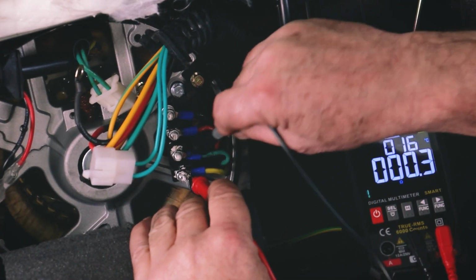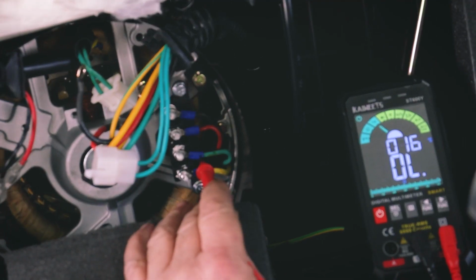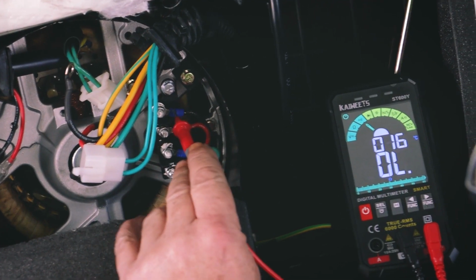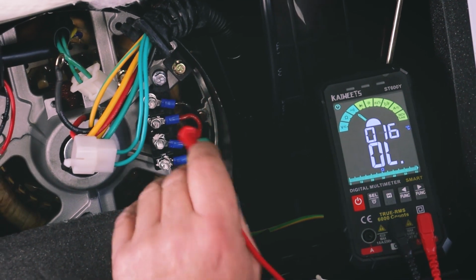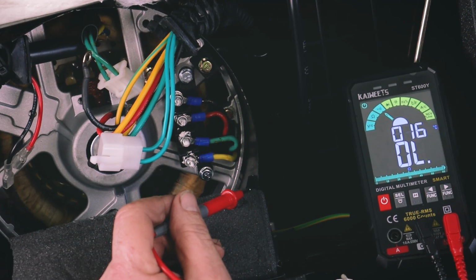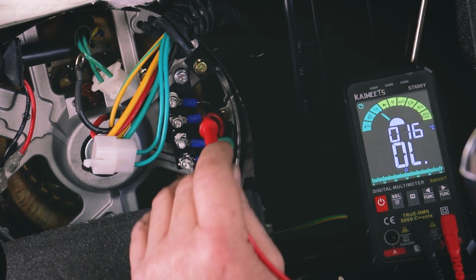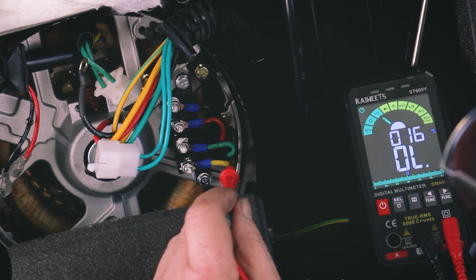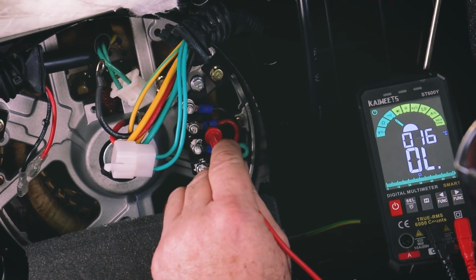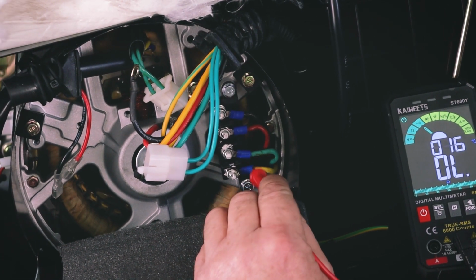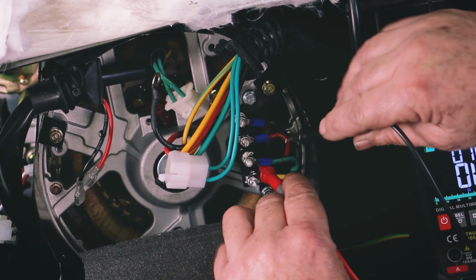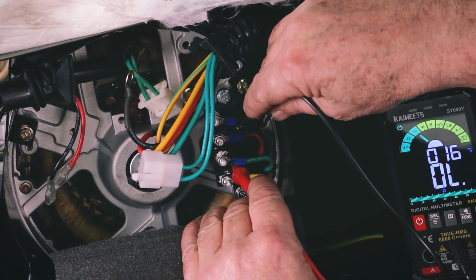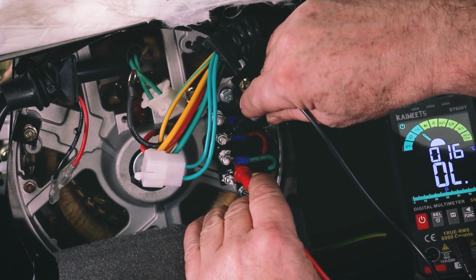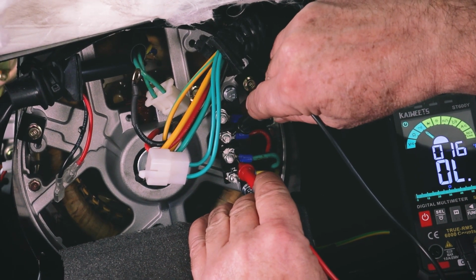Good. Okay. Now then, if I don't have continuity there, or I don't have continuity there, then we're in the dark hole of having to change the alternator, and that is what is at fault. Okay, so that's step 1. Let's say we get continuity across those 2. We get it across those 2. We should not have continuity between the 2 sets of windings. So if I go between the green and the red, there should be nothing.